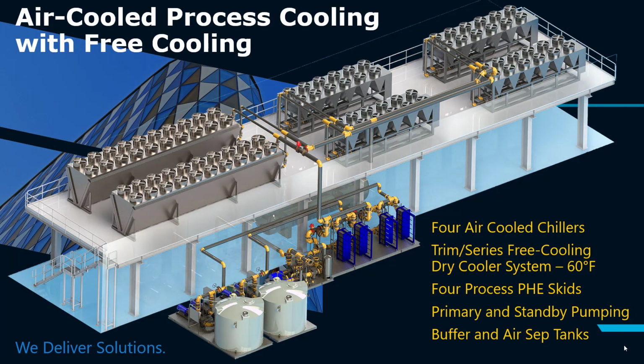Let's take a look at some applications that Fluid Cooling Systems has manufactured. This one has 4 air-cooled chillers here, and this is 2 banks of trim coolers that are set for a 60-degree set point, so that when the temperature hits 60 degrees, you'll start having some flow take place through these dry coolers, through these free coolers, to trim the load going to the chillers.